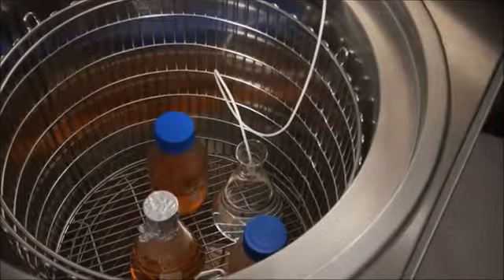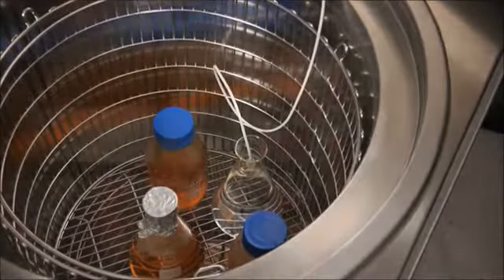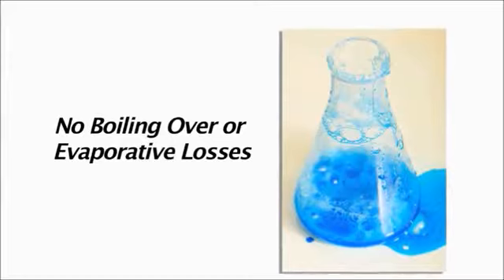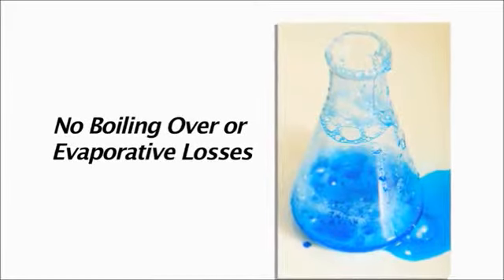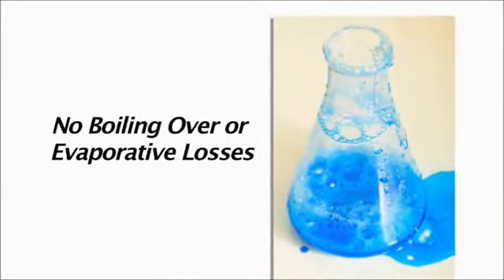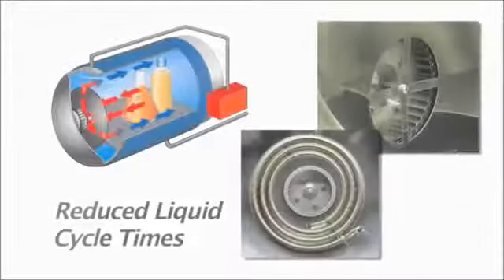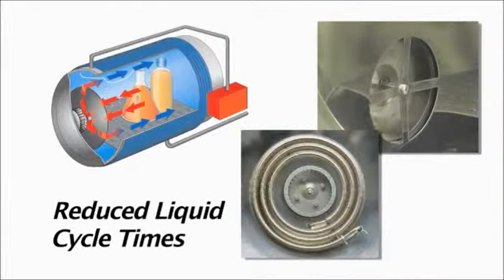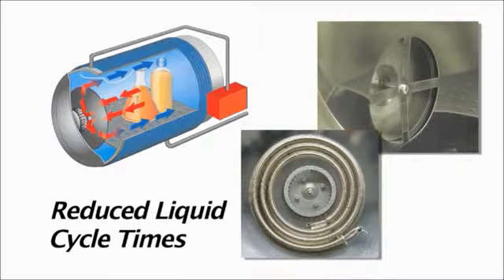Systec autoclaves are designed to have a flexible temperature probe directly in the unit. You can place this into a reference vessel so you can actually monitor the temperature of the liquid to be sterilized. Most benchtop autoclaves that a customer would buy are truly dental autoclaves that have been morphed into a laboratory system. However, they were really not efficient for that application. Unlike other autoclaves, liquid sterilized with Systec will not boil over or suffer evaporative losses during the cooling phase. With a wide range of cooling options available, liquid cycle times can be dramatically reduced, allowing for daily high volume throughput.